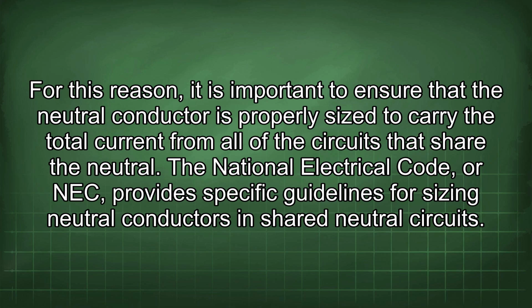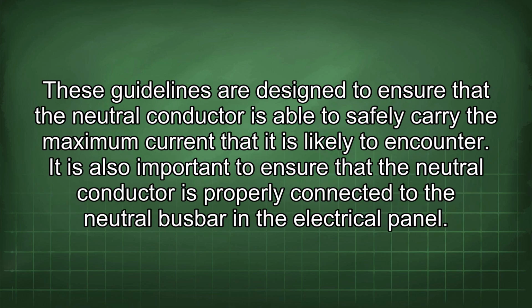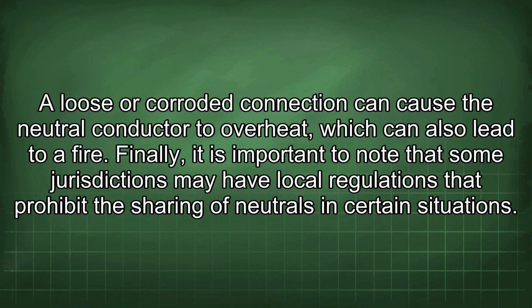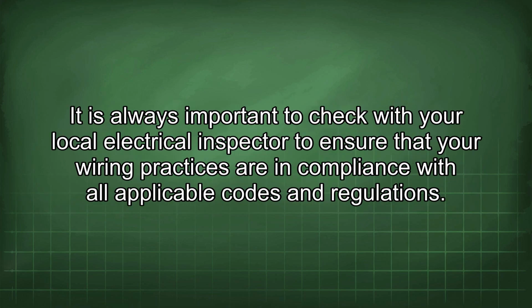The National Electrical Code, or NEC, provides specific guidelines for sizing neutral conductors in shared neutral circuits. These guidelines are designed to ensure that the neutral conductor is able to safely carry the maximum current that it is likely to encounter. It is also important to ensure that the neutral conductor is properly connected to the neutral busbar in the electrical panel. A loose or corroded connection can cause the neutral conductor to overheat, which can also lead to a fire. Finally, some jurisdictions may have local regulations that prohibit the sharing of neutrals in certain situations. It is always important to check with your local electrical inspector to ensure that your wiring practices are in compliance with all applicable codes and regulations.